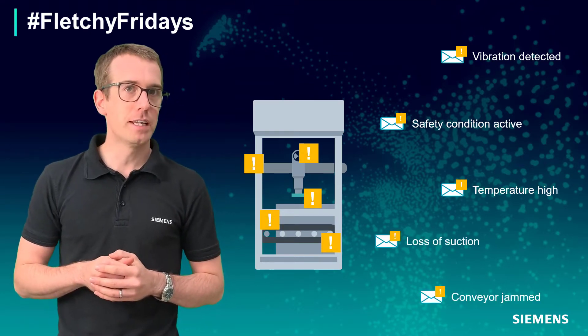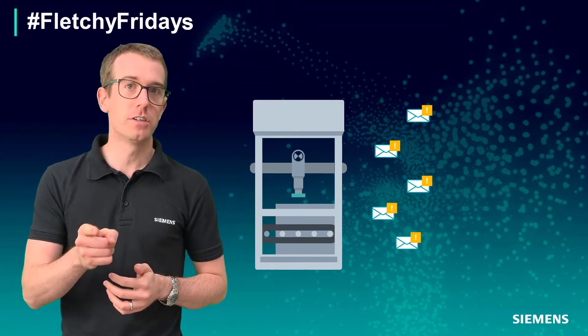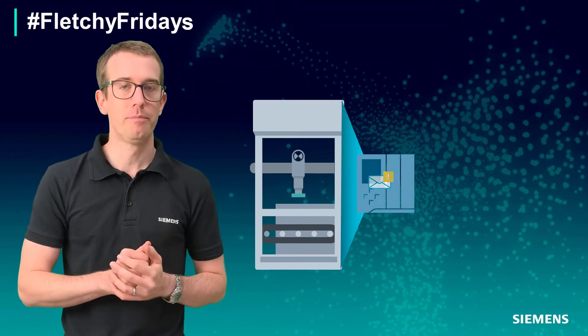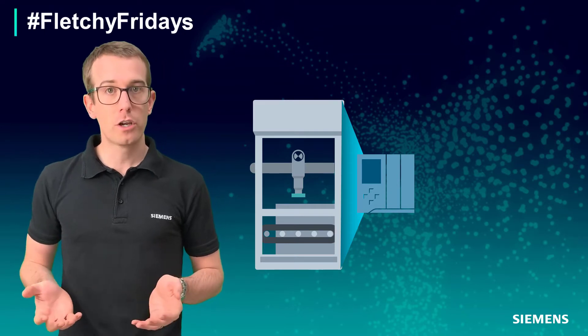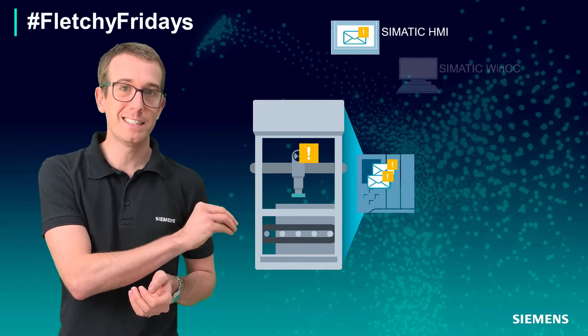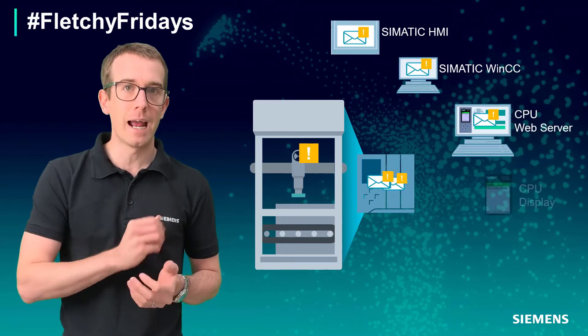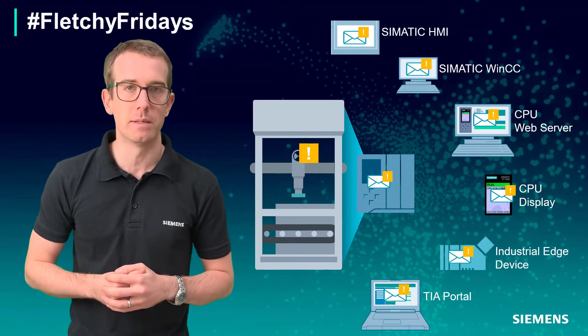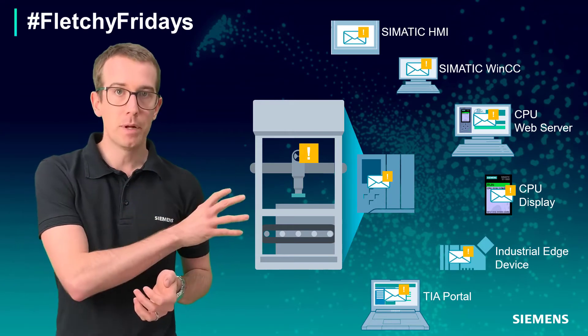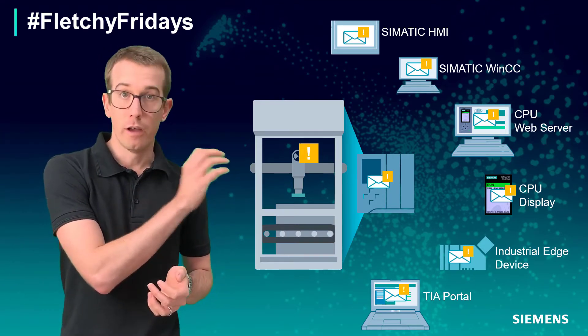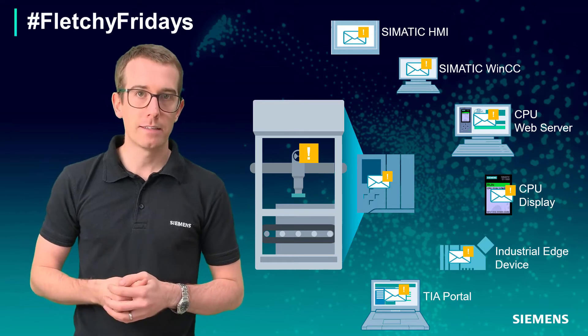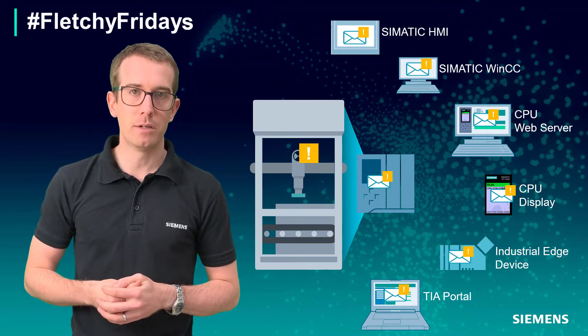ProDiag allows you to centralize the creation of your alarm messages within the S7-1500 application code, meaning that if a fault does occur in operation, the S7-1500 is going to issue a consistent alarm message out to the connected visualization systems — be it our HMIs or SCADAs, the inbuilt CPU web server, the edge devices, or even to TIA Portal, the engineering software, which has an alarm display built in as well.